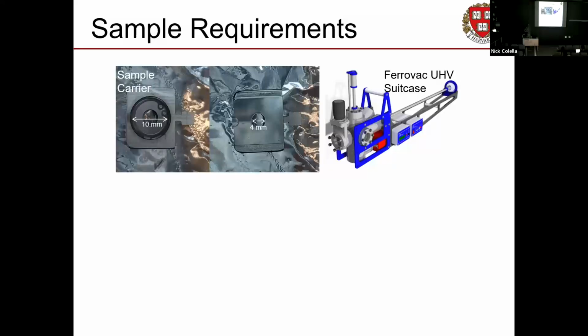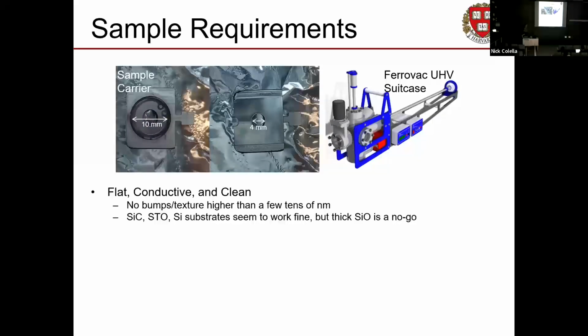So that's a little tedious. But okay, we have mounting tricks to make this work if your sample doesn't fit in those sizes. If your sample is smaller than 4 millimeters, you've got mounting tricks. If it's bigger than 10 millimeters, I've got half size. No worries, make it work. Your sample needs to be flat. It needs to be flat because if it's not flat and we put 15 kilovolts on it, you're going to get diverging field lines coming off all the bumps, and your electrons are going to get bent off to the side, and they're not going to go back up through the lens, and we're not going to get a picture.